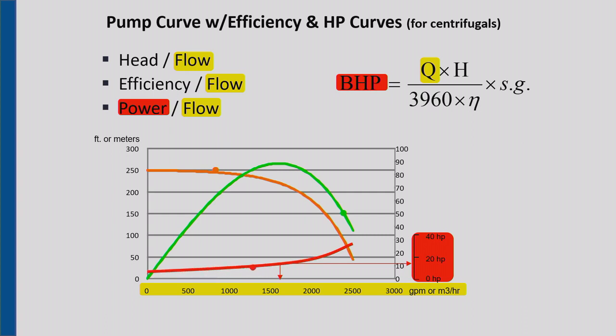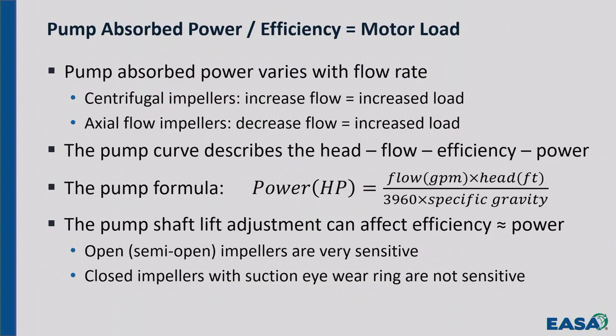Okay. All right. That's important because you're going to get that call from the customer that says, hey, your motor's pulling high current. Just repaired it. Send it into you. Send it back. And this is where you have to go. This is your first question when it says high current on the motor. What's the head? What's the flow? Going to get a copy of the pump curve. Okay? All right. Let's see. So that was the pump curve and the pump formula.